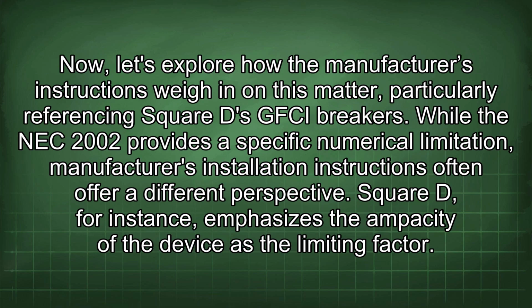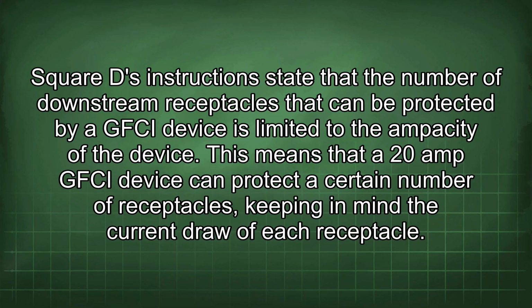Now let's explore how the manufacturer's instructions weigh in on this matter, particularly referencing Square D's GFCI breakers. While the NEC 2002 provides a specific numerical limitation, manufacturer's installation instructions often offer a different perspective. Square D, for instance, emphasizes the ampacity of the device as the limiting factor. Square D's instructions state that the number of downstream receptacles that can be protected by a GFCI device is limited to the ampacity of the device.